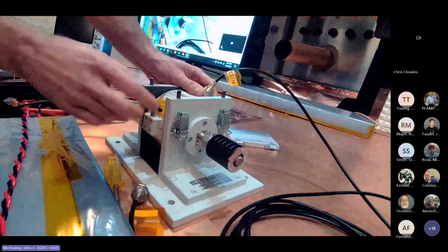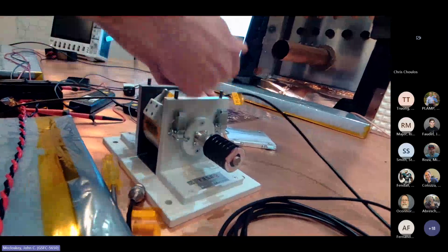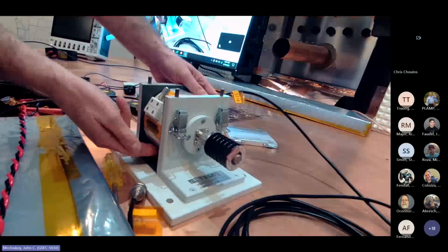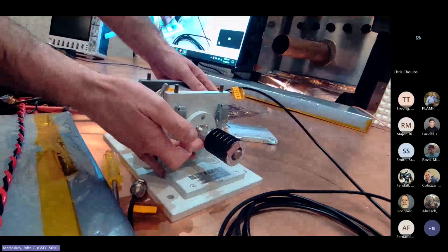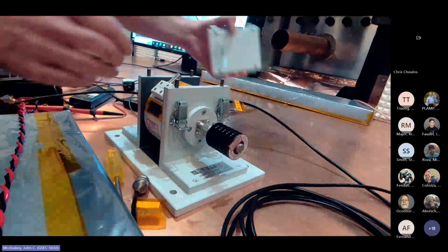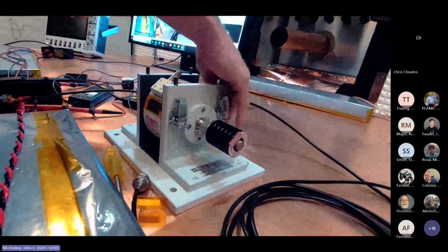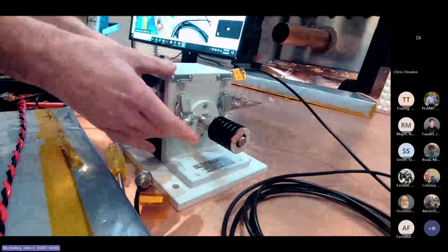Okay, so it's just a simple coil of wire wrapping around that magnetic core that induces that magnetic flux that goes through the loop here between the center conductor of the calibration fixture and the base. And so it's very simple, at least conceptually. So we'll put our lid back on.